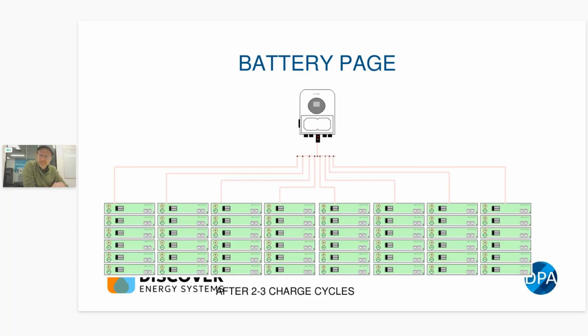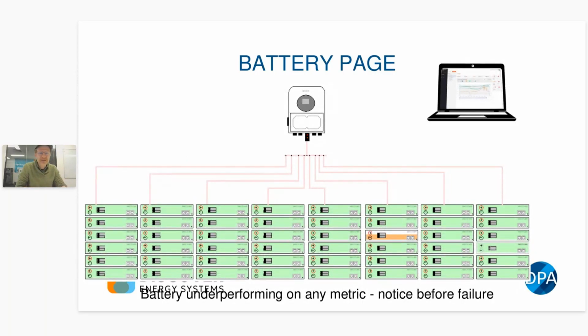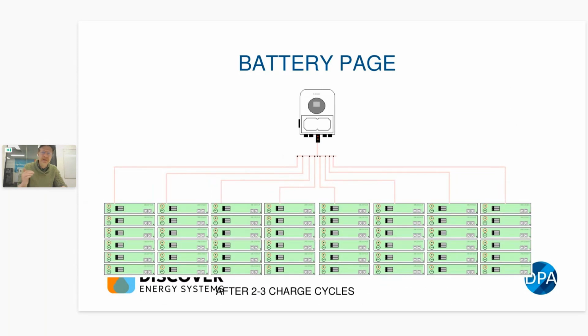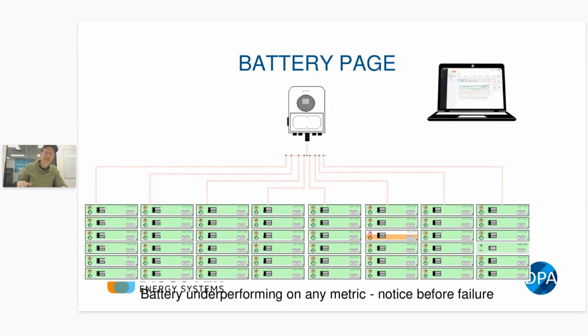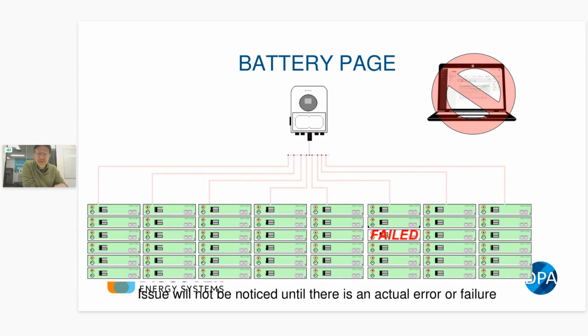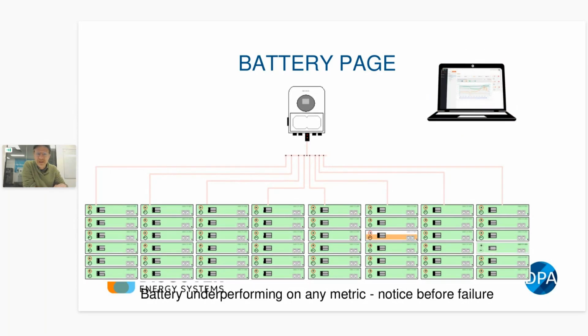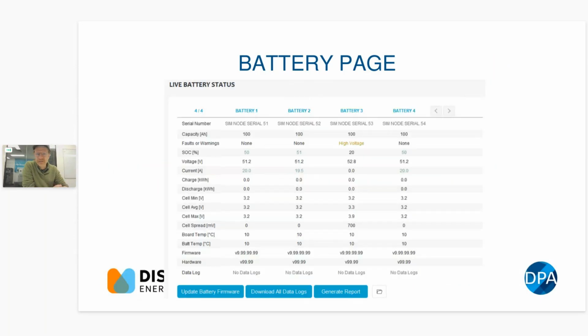So the example being, you put a big bunch of batteries into a system and you're hoping that they're all at the same state of charge, but really to begin with they're going to be all over the place. You normally don't have visibility on that, but with the system you can see if one of them is at a different state of charge to the rest, which means it's going to possibly have an issue down the track. You'll be able to see that before it happens and plan to go to site or look at it online and get some support before it actually fails and you've got a customer complaining to you.